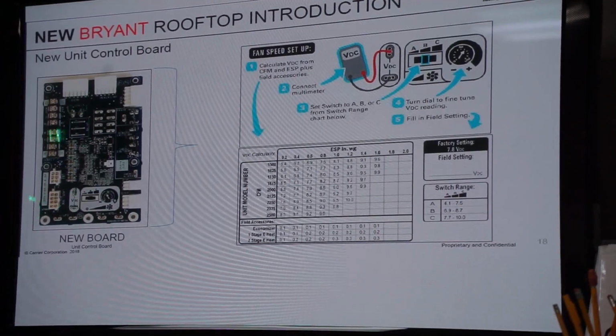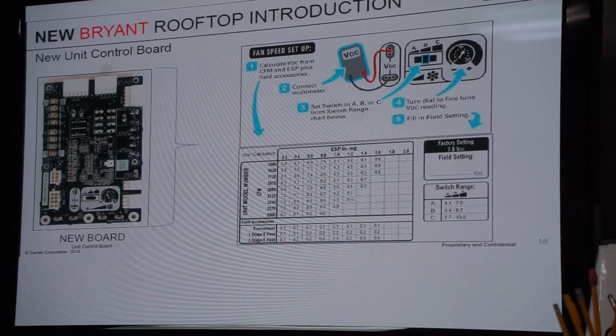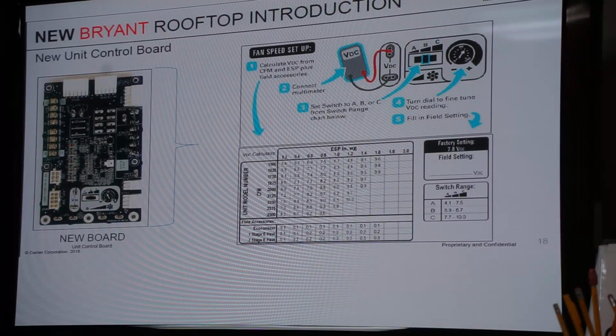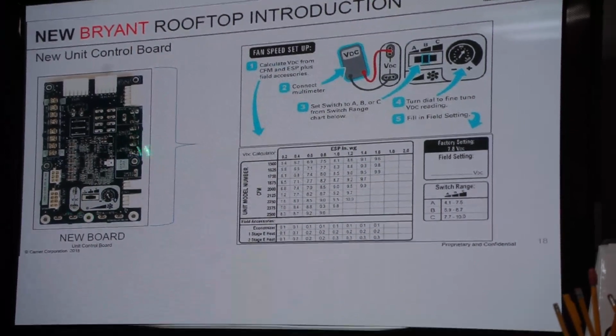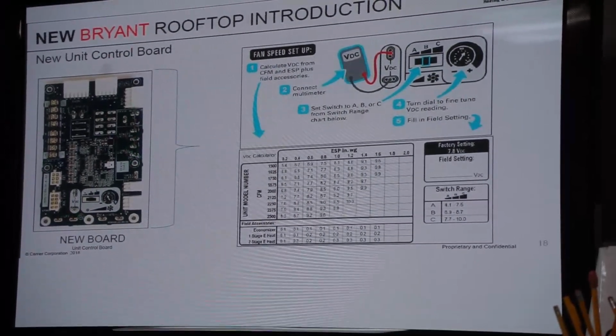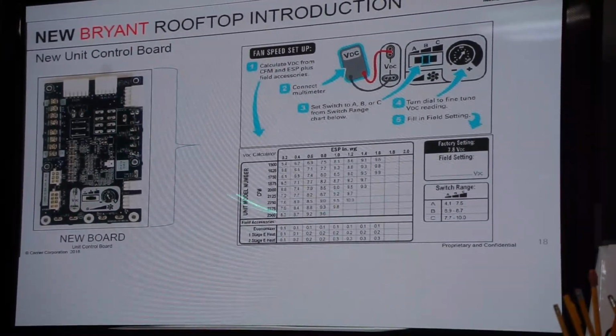This is our terminal board. Remember how I said there's nothing on the back of the older style? It's just pathways. This has got a potentiometer on it now, so there is a little bit more on it. This is our terminal where we're wiring our thermostat. This is our smoke shutdown and our occupied. If I was to put that stat in there, I would take off one of these jumpers for occupied, and then also if I've got a building smoke alarm in there, that's where I would wire it.